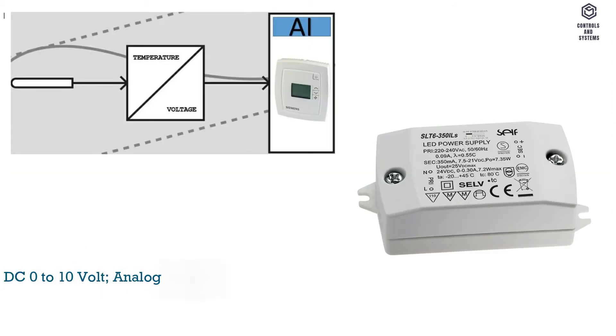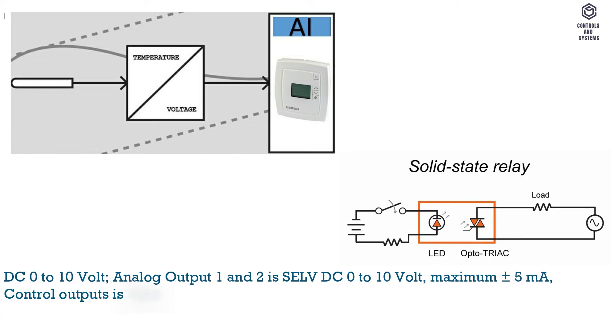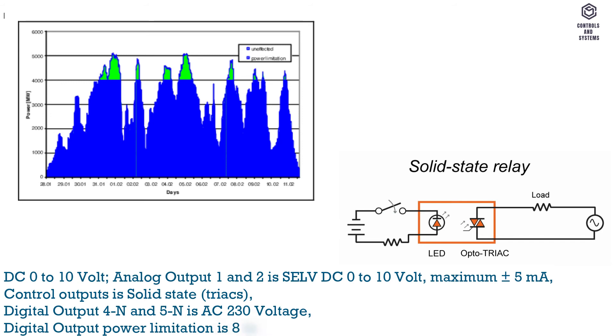Digital outputs rating: minimum 5 mA, maximum inductive 2 A. No internal fuse — always use external protection with a maximum C10 A circuit breaker in the supply line. Do not connect fans in parallel; connect one fan directly. For additional fans, use one relay for each speed. DC 0–10 V analog outputs 1 and 2: SELV, DC 0–10 V, maximum ±5 mA. Control outputs are solid-state TRIAC, digital outputs 4 and 5 at AC 230 V. Digital output power limitation is 8–300 mA, 3 A fast micro fuse — cannot be exchanged.